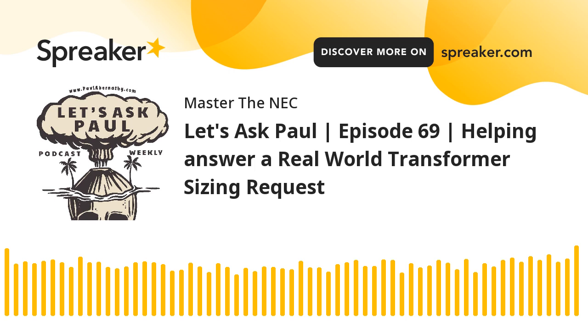But you also could come off those secondary terminals at the transformer and hit a disconnect for that HVAC unit, which is also a circuit breaker, which is also going to have the overcurrent protection and everything else that's required for that HVAC unit. And it's going to serve as the disconnecting means and all that wrapped in one. But one of the caveats is those conductors have to terminate into a single circuit breaker. So the question of whether it's fused or unfused that I think you ask later is irrelevant because it has to terminate into a circuit breaker or a single set of fuses. All of this has to limit the load to the ampacity of those conductors.